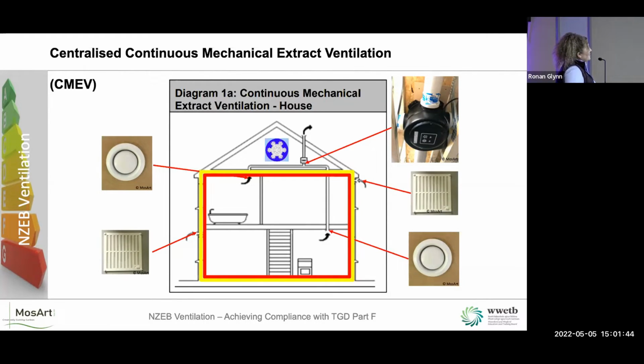Part F really gets down in the weeds when it defines what insulation you should have on the ducts in the attic. It also says that you must insulate this upstand on the ductwork, because you don't want the condensation running back down into the unit. But there's no heat recovery. This is where it ticks all the boxes for Part F, but doesn't really go with conserving fuel and energy.